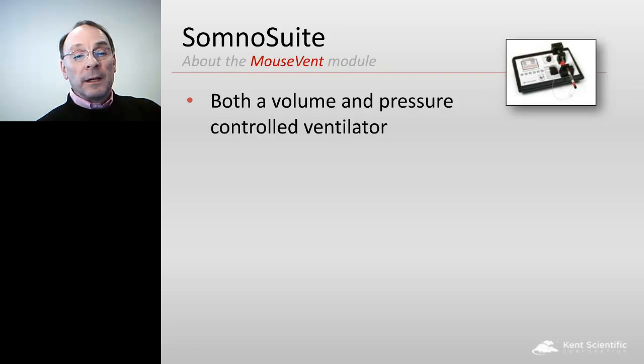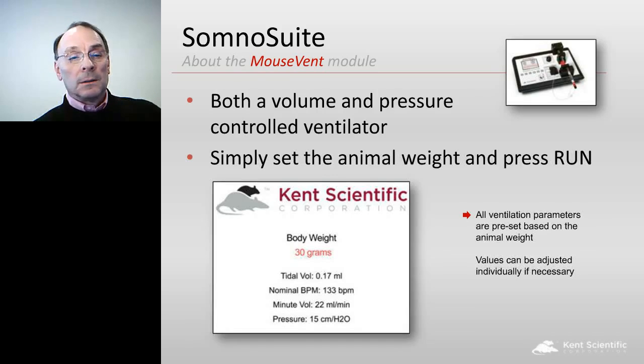The ventilator, which is called the mouse vent, is both volume and pressure controlled. It's simple to set up. The system was designed to make it tremendously easy. The default ventilation pressure is 15 centimeters of water, which is a safety parameter. It dials in, so that's the maximum pressure that the animal will get. And then, using allometric formulas, the user just has to dial in the weight of the animal, and the formulas are used to determine the respiration rate and also the tidal volume and minute volume that the animal should be getting.